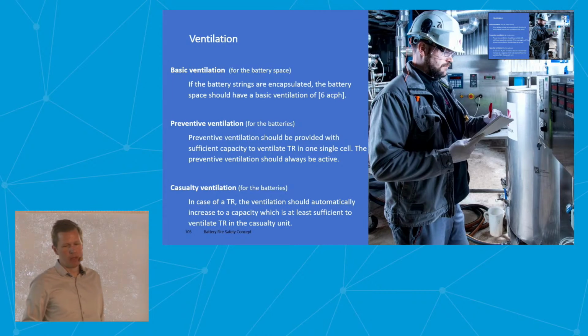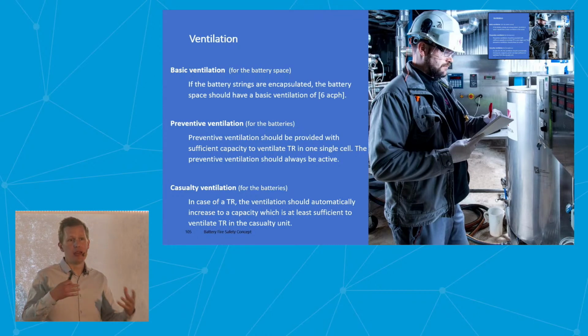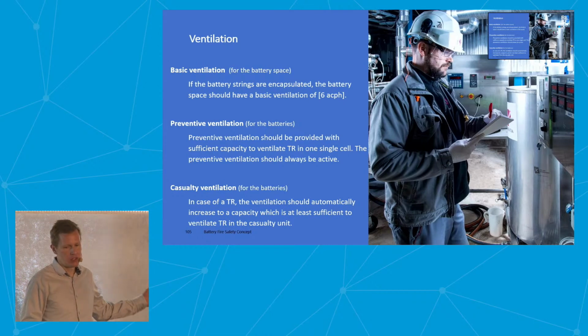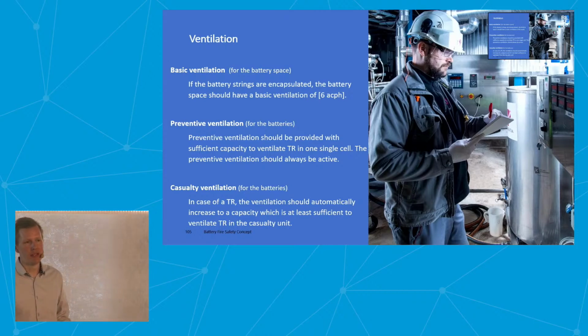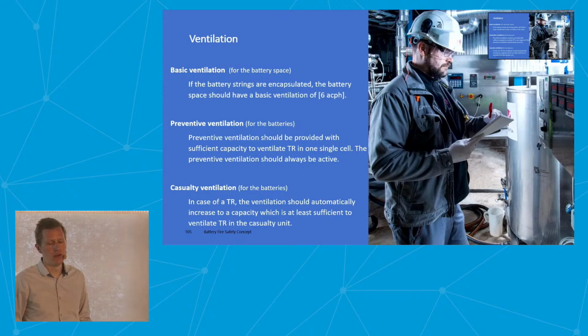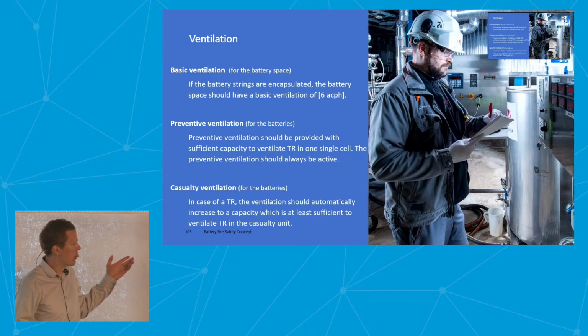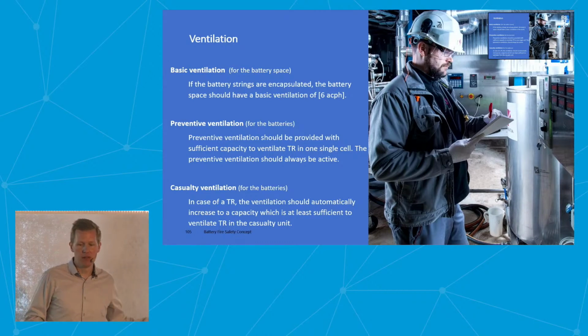The preventive ventilation should be able to handle gases from one single cell - that should be the minimum for the batteries. Then the casualty ventilation, as we call it, you should be able to increase the capacity in case of detection of a failure, to handle this unit, whatever it is.